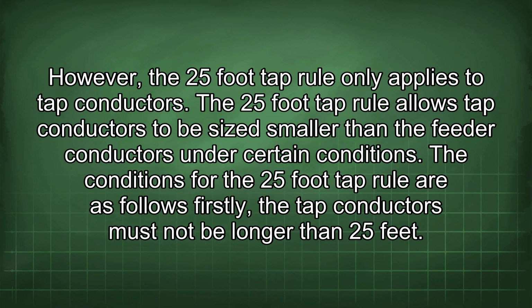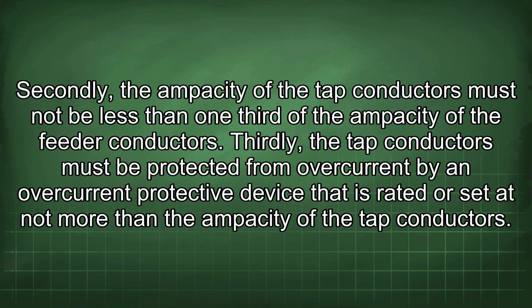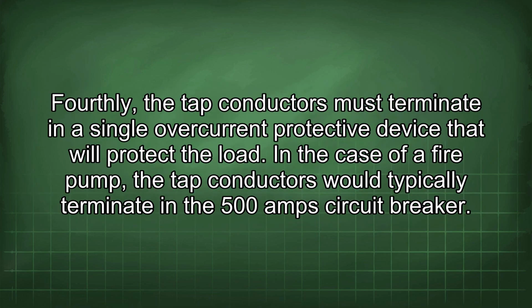The conditions for the 25-foot tap rule are as follows. Firstly, the tap conductors must not be longer than 25 feet. Secondly, the ampacity of the tap conductors must not be less than 1/3 of the ampacity of the feeder conductors. Thirdly, the tap conductors must be protected from overcurrent by an overcurrent protective device that is rated or set at not more than the ampacity of the tap conductors. Fourthly, the tap conductors must terminate in a single overcurrent protective device that will protect the load.